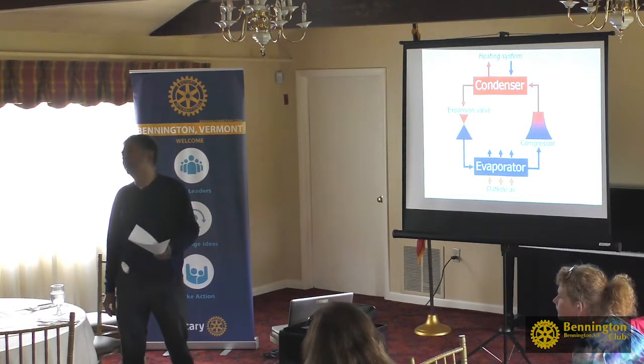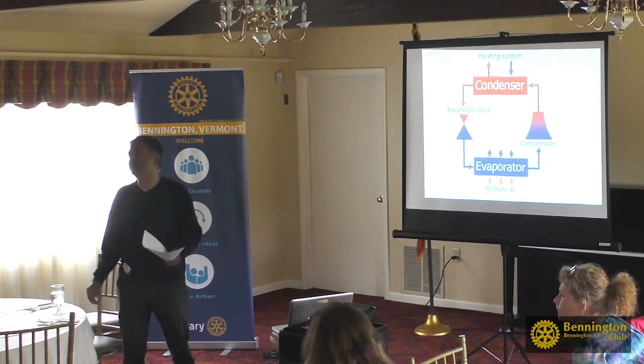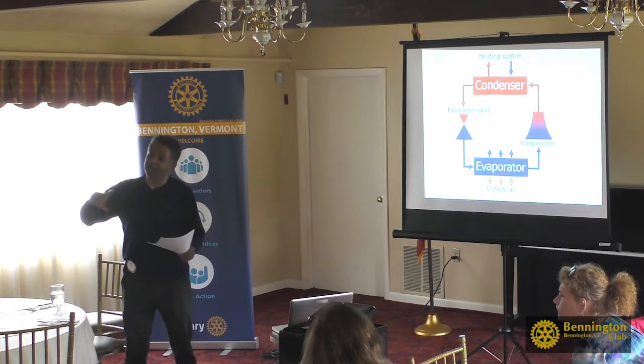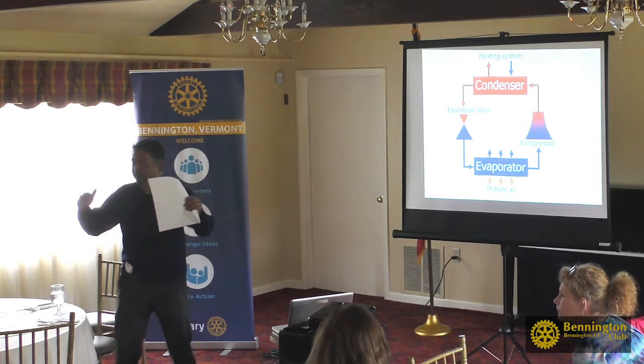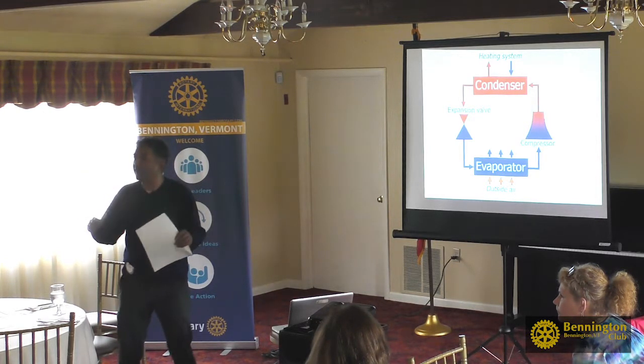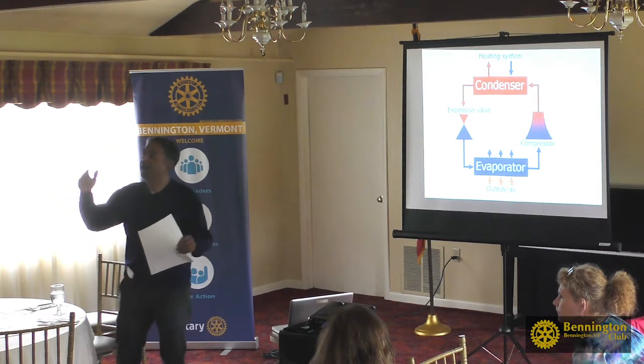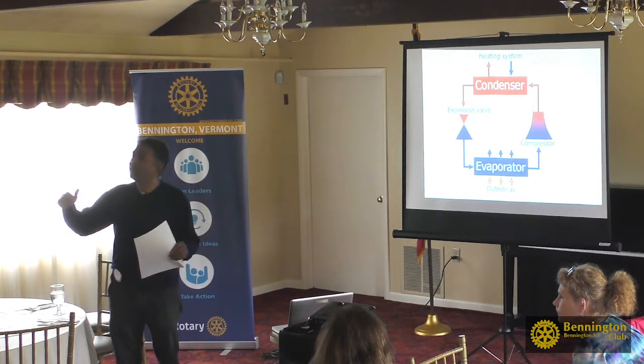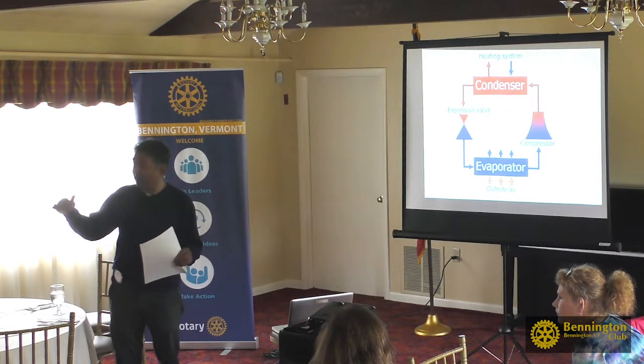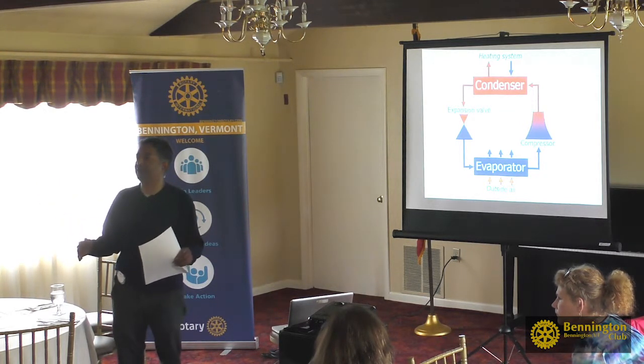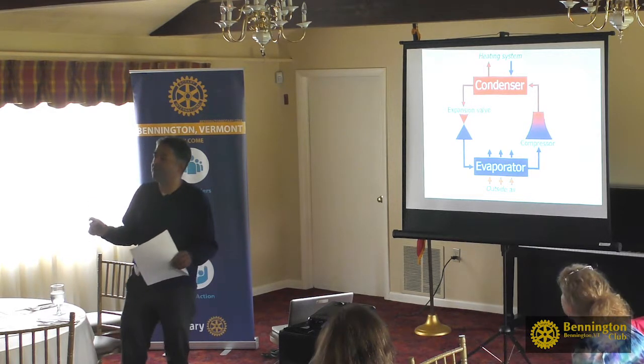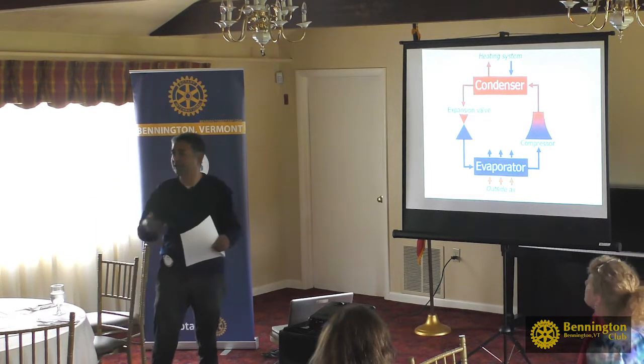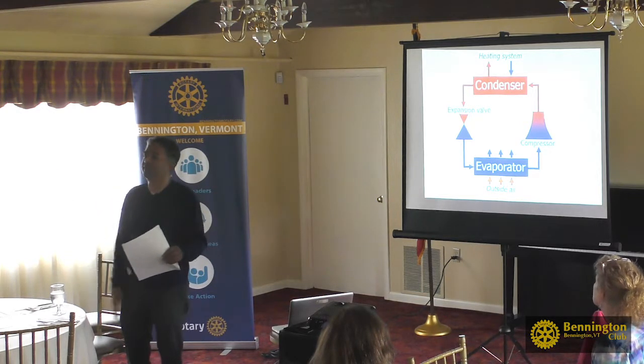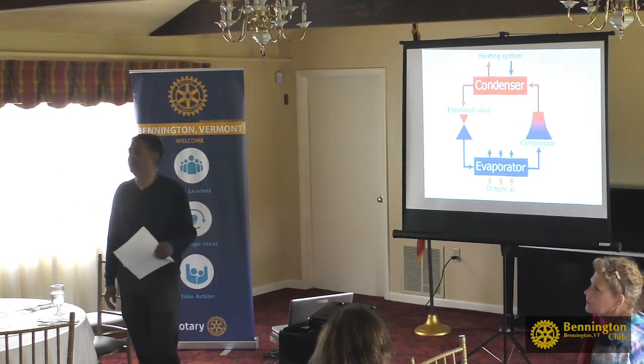A variable speed drive. It's a very high efficiency motor coupled to a device that can slow the fan down rather than shut it off. There's a law that says as you turn fans down, energy usage does not drop in proportion to how slow you turn the fan down. If you turn it down by 50%, energy usage becomes about 12%. So it's a very, very high efficiency fan that drives and blows across the refrigerant, the condenser, and the evaporator. The fan power does come from the grid.